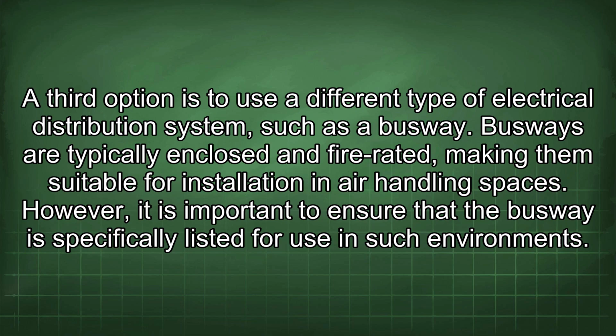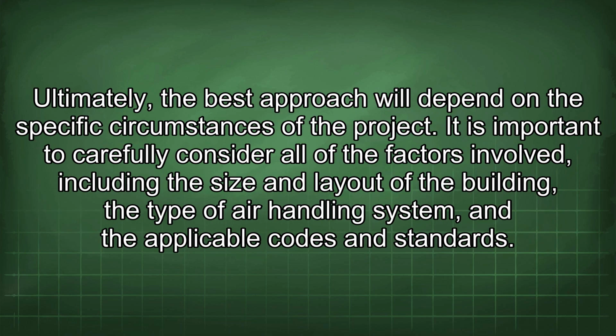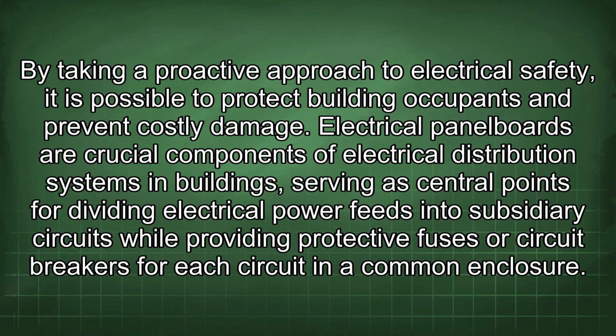A third option is to use a different type of electrical distribution system, such as a busway. Busways are typically enclosed and fire-rated, making them suitable for installation in air handling spaces. However, it is important to ensure that the busway is specifically listed for use in such environments. Ultimately, the best approach will depend on the specific circumstances of the project. It is important to carefully consider all of the factors involved, including the size and layout of the building, the type of air handling system, and the applicable codes and standards. By taking a proactive approach to electrical safety, it is possible to protect building occupants and prevent costly damage.